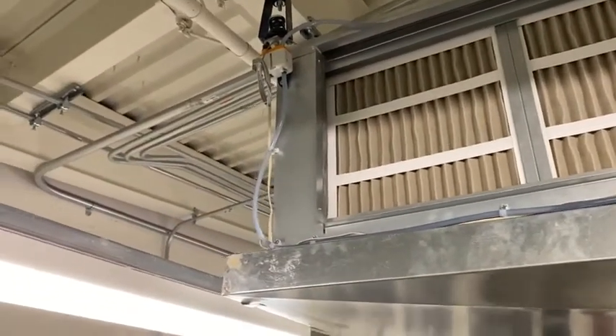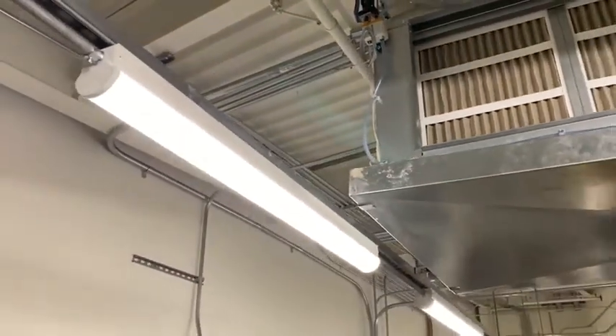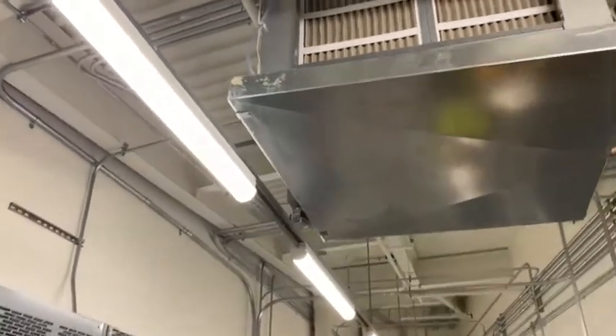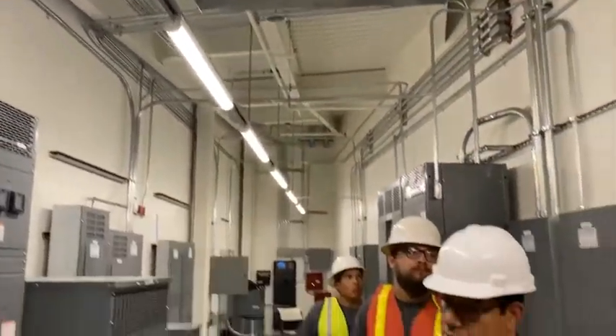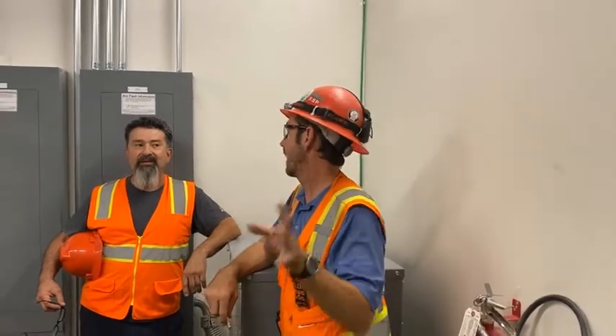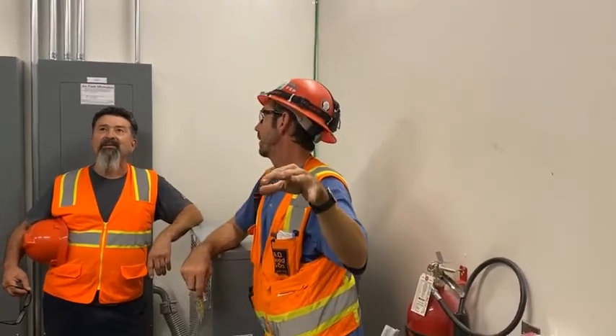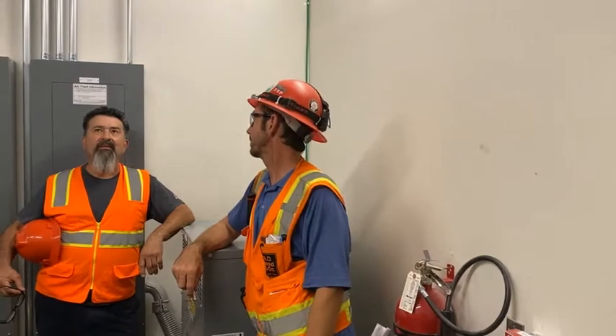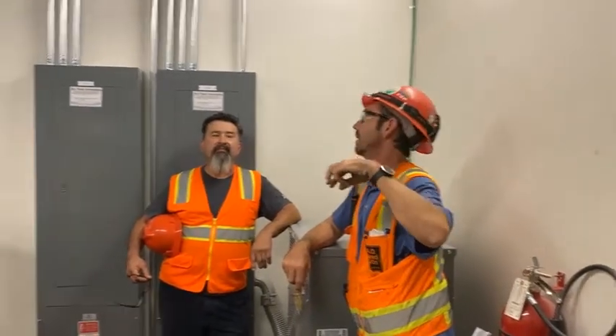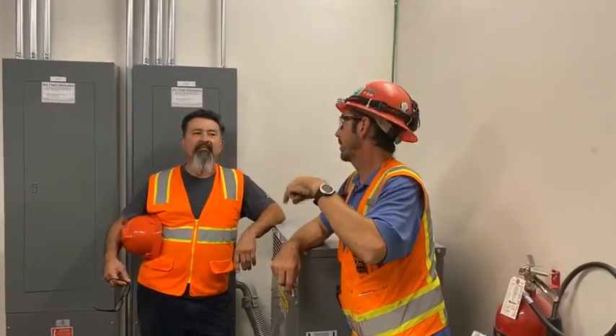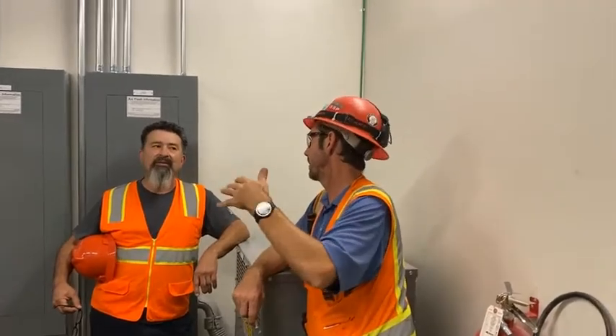They just hung this. We'll make sure we get that rerouted 90 to the wall and then run down to the floor. The alarm will just be a tattletale. For our contract, it'll just go over to the wall and down to the wall. Eventually, if you guys want to add some type of a switch in there, you can, but you need to plug that open. Unless you have an electronic moisture sensing switch, if it's a float style switch, obviously that won't work.